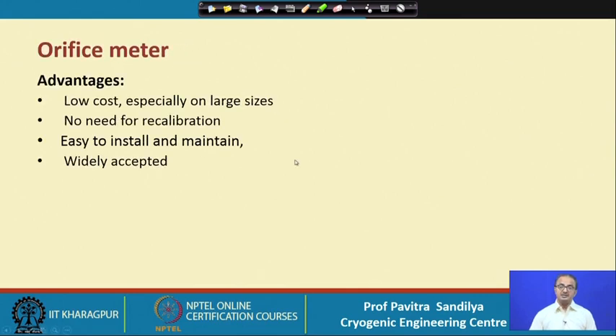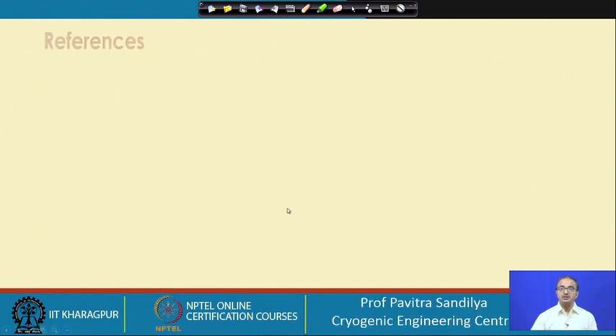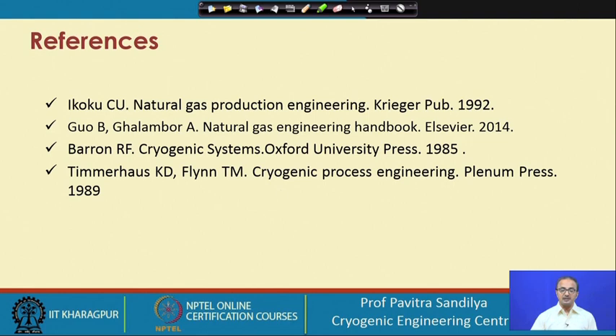The advantages of the orifice meter are: low cost especially for large sizes, no need for calibration, easy to install and maintain, and widely accepted. The disadvantages are: poor turndown ratio (the ratio between maximum and minimum acceptable flow rates), long installation requirements of about 20D to 30D (where D is the pipe diameter), and accuracy dependent on geometry. More detail can be obtained from the references provided.